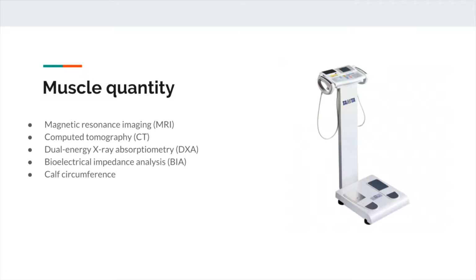The dual energy X-ray absorptiometry, or DXA, is a more widely available instrument to determine muscle quantity, and it is not invasive. However, different brands do not give consistent results. DXA is favored by some clinicians and researchers for measuring muscle mass. The advantage of DXA is that it can provide reproducible results when using the same instrument and cutoff points in a few minutes. A disadvantage is that the instrument is not portable yet. In addition, DXA measurements can be influenced by the hydration status of the patient.